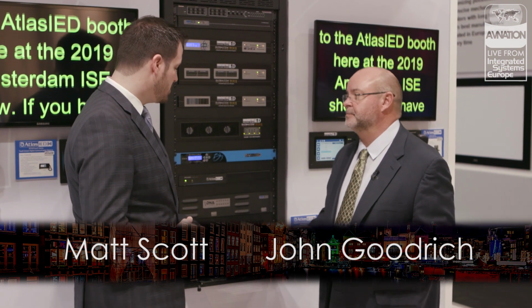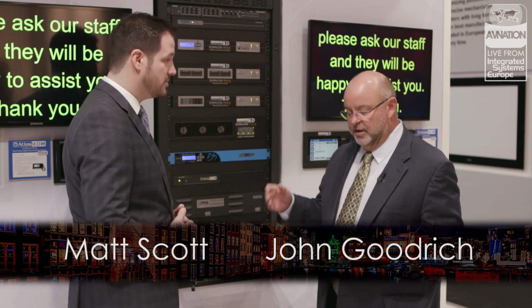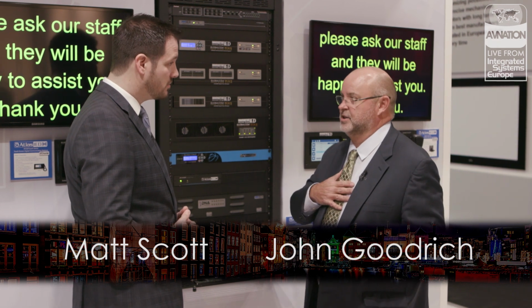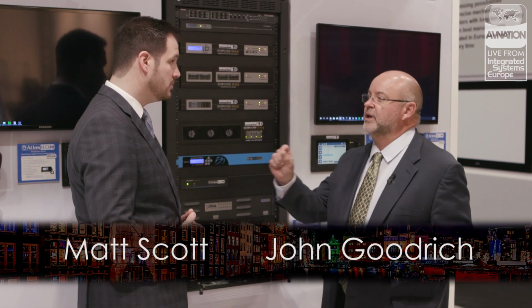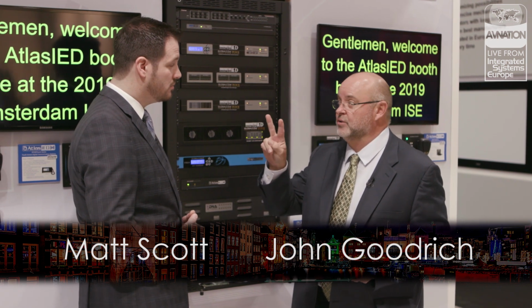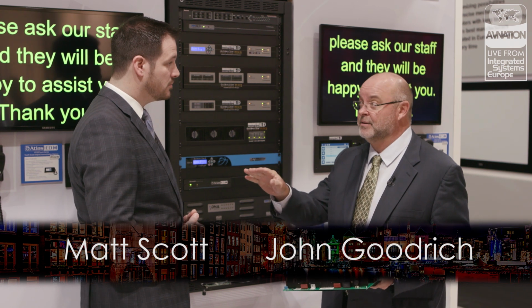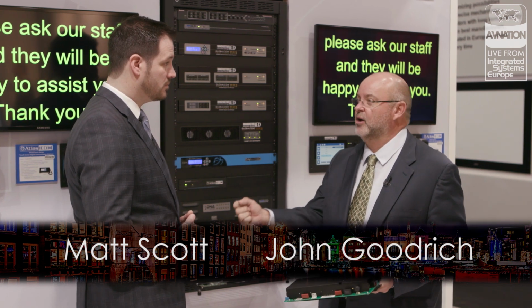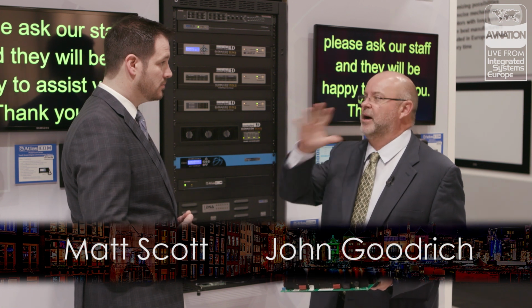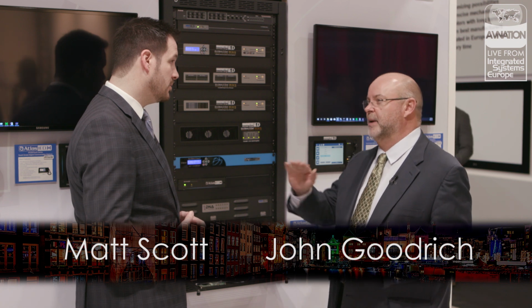So when we start talking redundancy, is this auto fail over, or do I need to send a technician out to hot swap these amps? If you have an amp fail, you'll get an SMS text. But the amplifier will pop in immediately. It does 2 cycles of failure. It does it at the zero crossing, so you hear virtually no pop. And when you put it back in, the replacement amplifier also waits for the zero crossing and pops right back in. So it's less than a 16th of a second typically. Depends on the sampling rate.